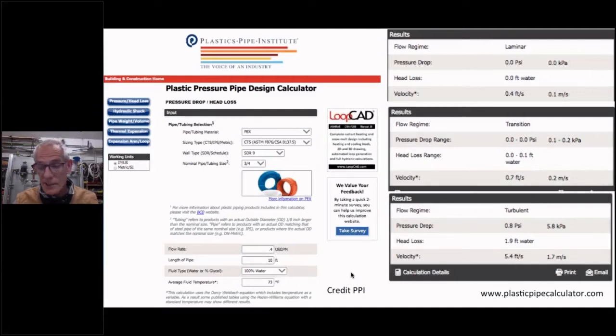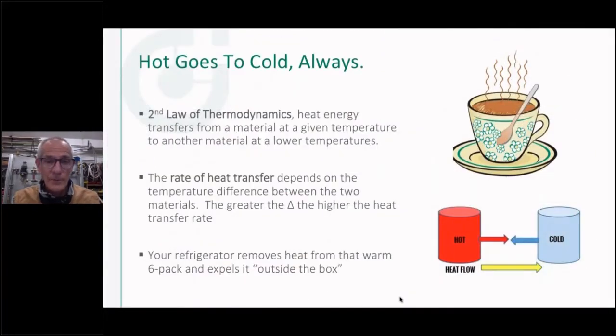We have those charts that are just kind of rules of thumb, saying the maximum amount of flow that you could put in a 1.25 inch pipe, copper pipe, whatever it might be. But this would be something you want to use if you really want to get that number exact, where you don't have to guess and say, well, do I have to go from 1.25 inches to 1.5 inches? What would happen to my flow velocity if I went 13 gallons a minute through 1.25 inches instead of the recommended 10 gallons per minute? All these tools are out there. They're available for free for the most part. So, take advantage of them.